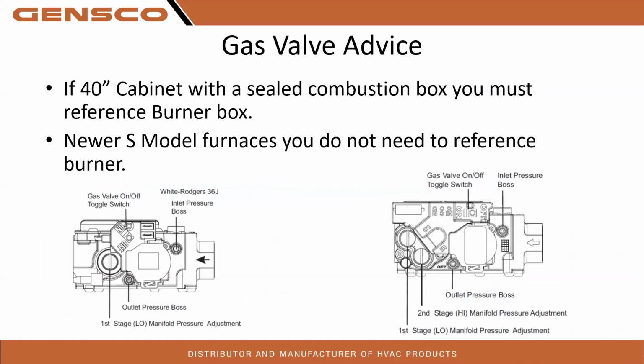So the advice on the current valves, S9V2s, are the White-Rodgers J valves. And these are the 36J single or two-stage. So most of the 40 inches have moved over to this style valve. Of course, the S8s, S9s are all this style valve as well. So remember, with the 40-inch cabinet, we still have to reference the burner. Doesn't matter the gas valve change.